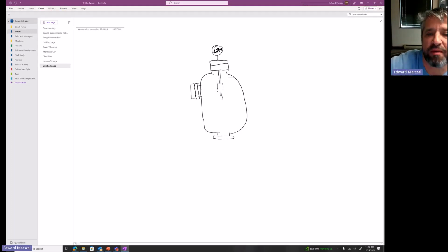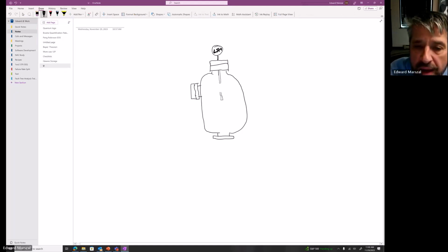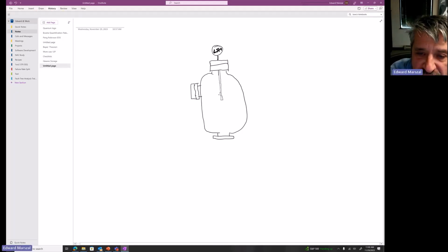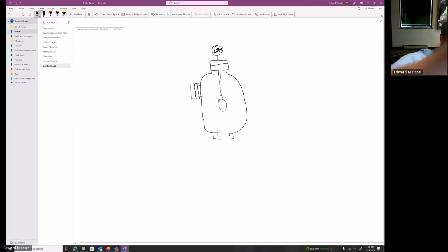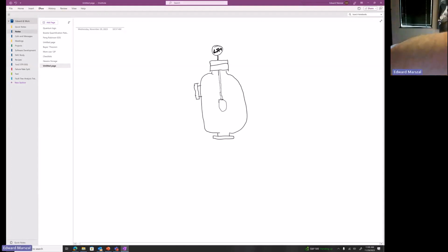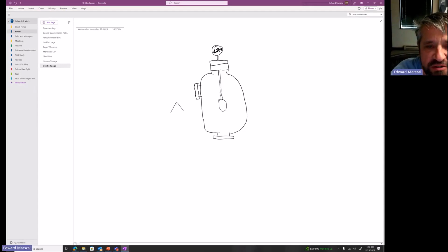So let me remove my level, and after I remove my level, now my float is sitting down here at the bottom. The tank is empty, my float's hanging out down there. How do I test this level switch to make sure it's working? Oh, I've got a great idea. I'm going to go out to the field. So I'm going to remove the blind flange on the manway. And I'm going to walk out. So this is me.